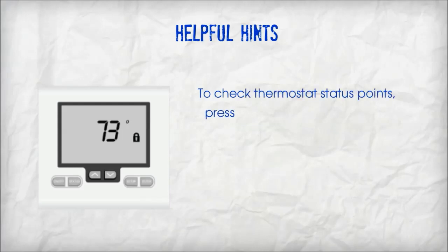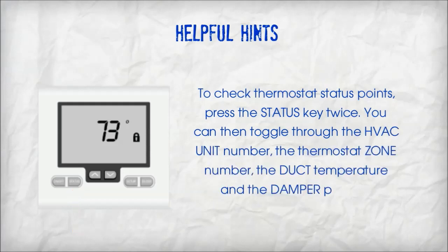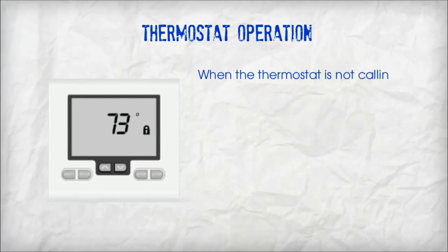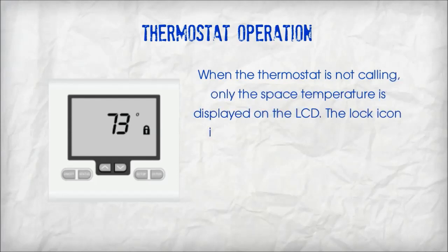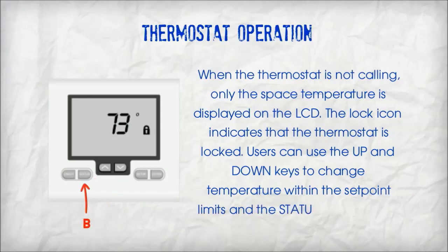To check thermostat status points, press the status key twice. You can then toggle through the HVAC unit number, the thermostat zone number, the duct temperature, and the damper position. When the thermostat is not calling, only the space temperature is displayed on the LCD. The lock icon indicates that the thermostat is locked. Users can use the up and down keys to change temperature within the set point limits and the status key to review the status points.